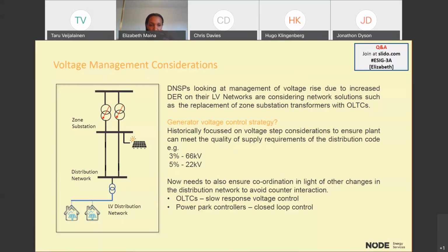A lot of the optimization for ensuring a distributed connected generator met quality of supply requirements was about ensuring voltage step fluctuations stayed within those limits. Now, as DNSPs consider the influx of distributed PV on their low voltage sections from rooftops, some solutions in their asset replacement programs may include replacing older zone substations with OLTC—on-load tap changers historically used at transmission levels.